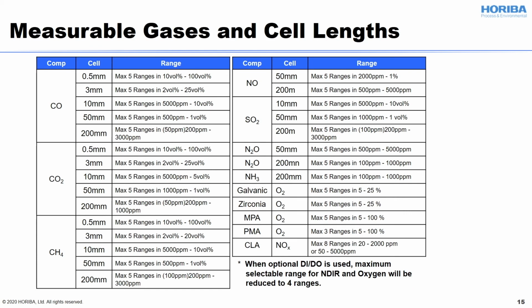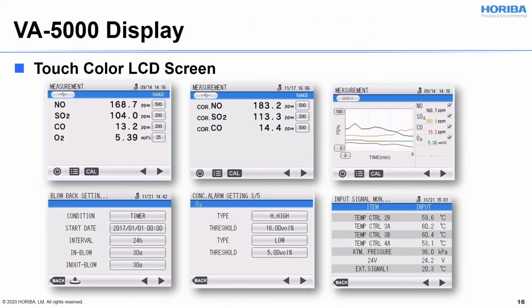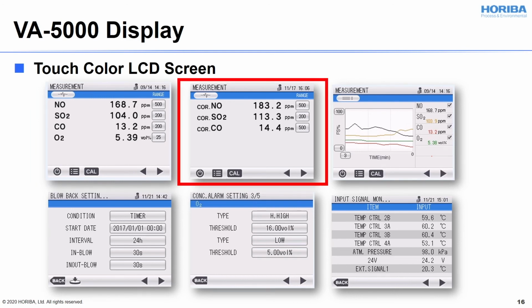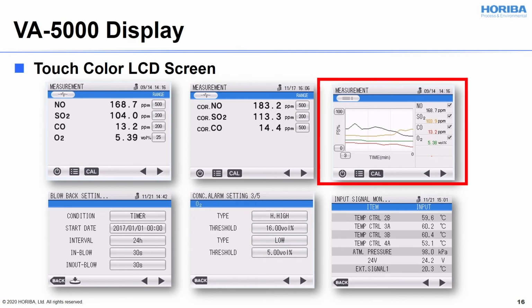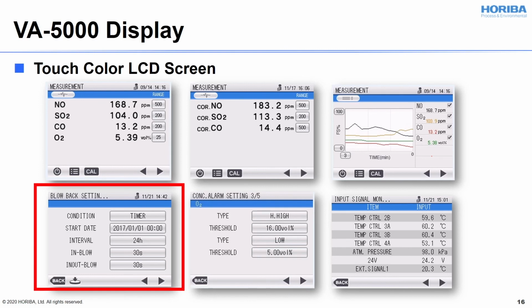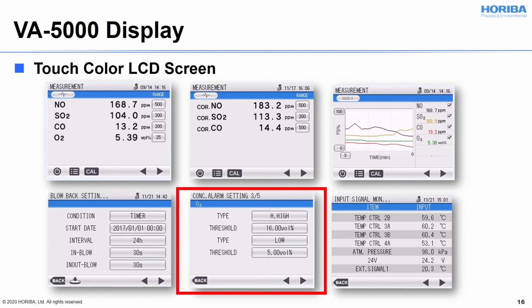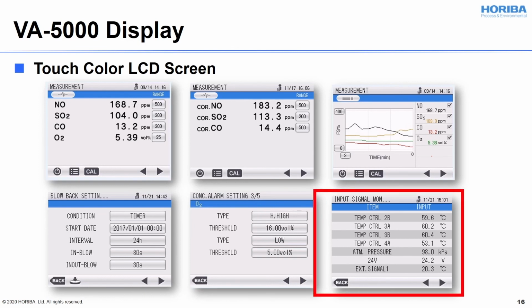So, for example, for a 0.5 millimeter CO cell, you can have a 10% to 100% range, and you can have 5 ranges between 10 and 100, like 10, 20, 50, 70, 100%. Okay, let's talk about the display and the menus. The main display shows the measurement information. You can see O2-corrected measurement data and graphing right there. For the settings, you can do a blowback setting, an O2 correction setting, and access the internal analyzer information.